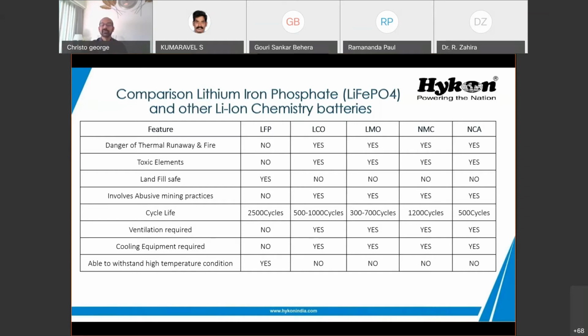It's not only that - the important thing to look at is cycle life. LFP cycle life is very high, 2,500 cycles, and even if depth of discharge is very low, this can go up to 5,000 to 8,000 cycles. It all depends on depth of discharge, which we'll explain. But LCO is only 500 to 1,000 cycles, LMO is 300 to 700 cycles, and new types of chemistry are coming every day. But these are the well-proven cells available in the market for the last 5 to 10 years.